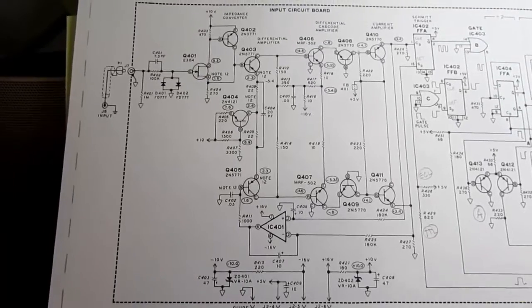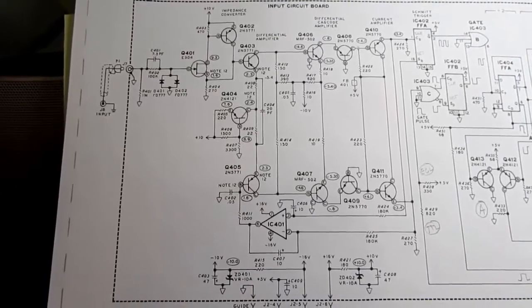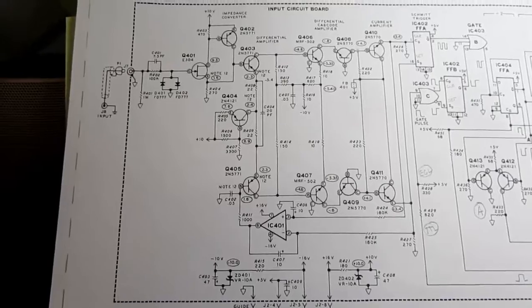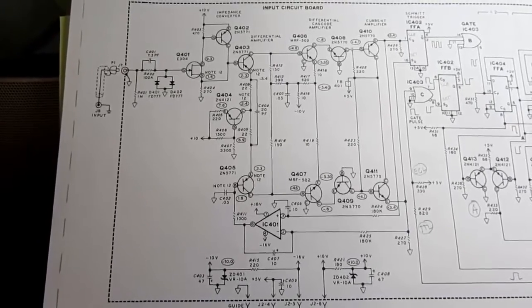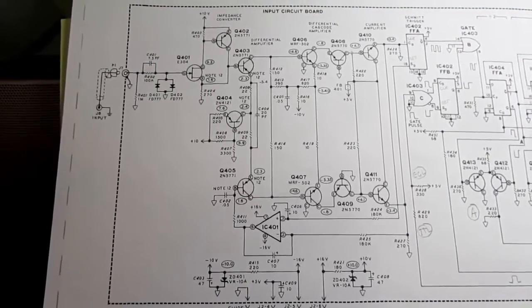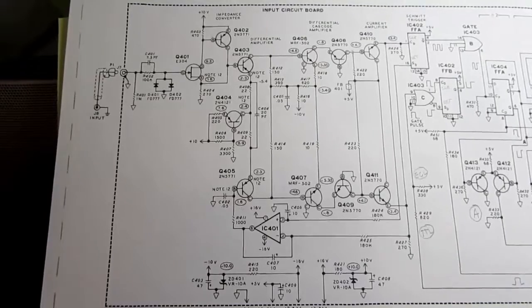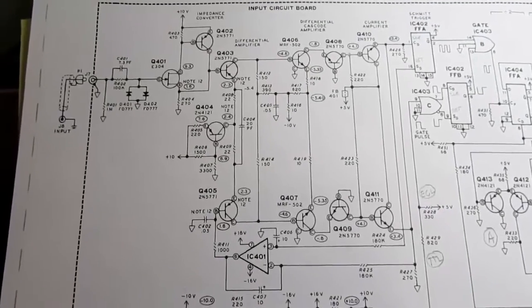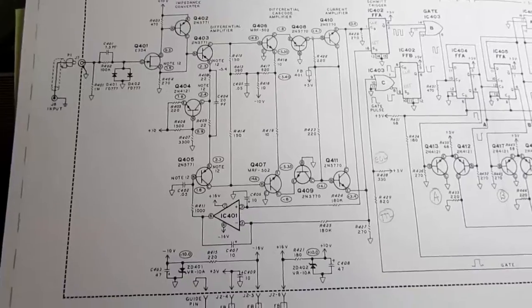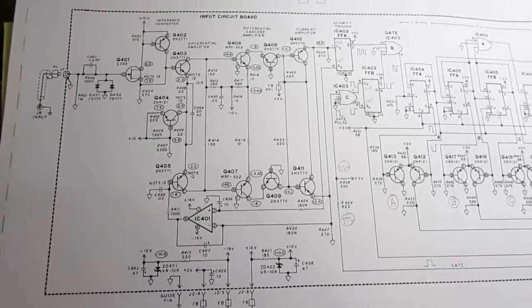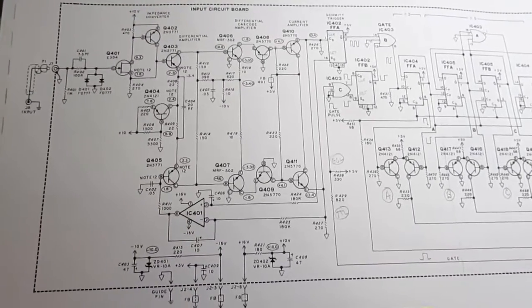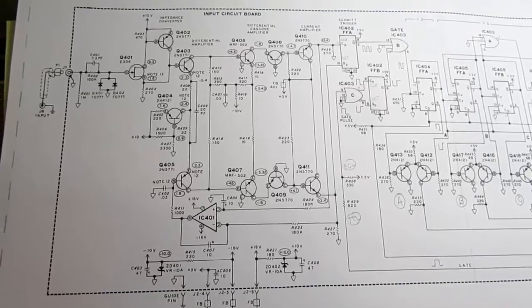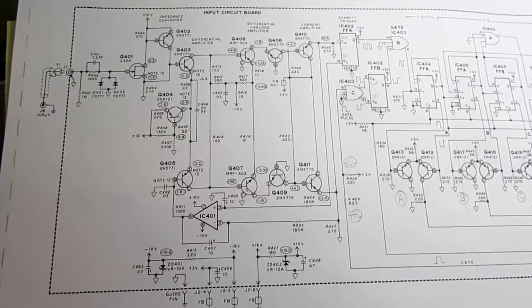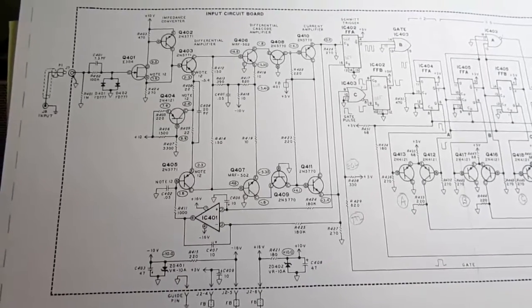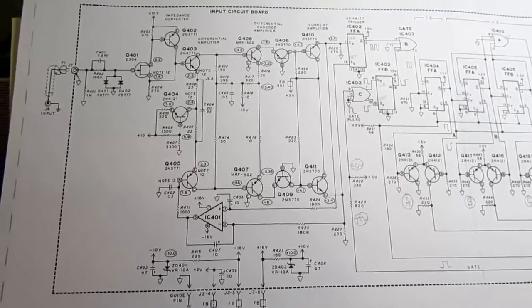So if you come in with a ramp signal or a sinusoidal wave or something like that, it needs to be conditioned to a square wave or a pulse wave with very sharp vertical transitions. So all those things have to be accomplished by this. Also, because this is a faster frequency counter, in its upper ranges it exceeds the ability of TTL logic of that time, before there was high-speed TTL and so on.